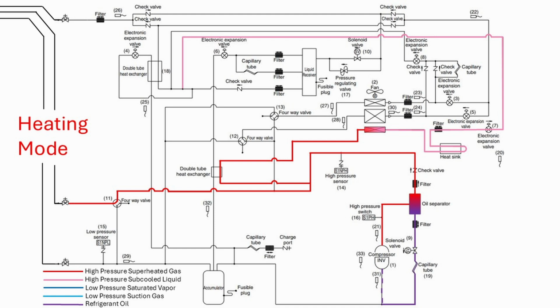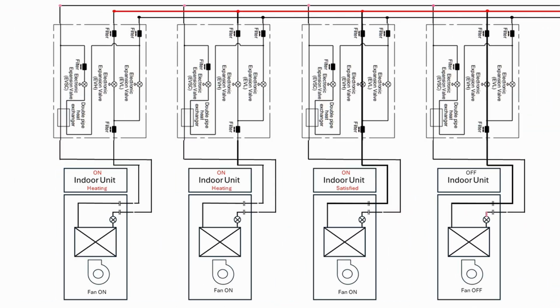The rest of the high-pressure vapor leaving the compressor is routed to the 4-way valve leading to the high-pressure line going inside to the branch selector box, then routed to the indoor units that are calling for heat. The branch selector is available in either a single, 1 indoor unit connected to 1 branch selector box, or multi, up to 12 indoor units connected to 1 branch selector. In this example, there is an individual branch selector box for each indoor unit.